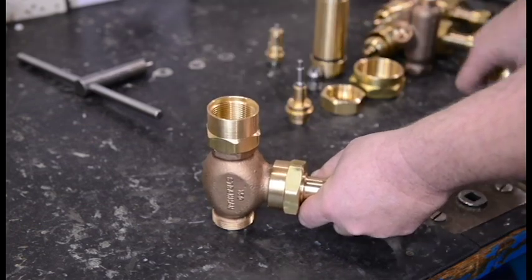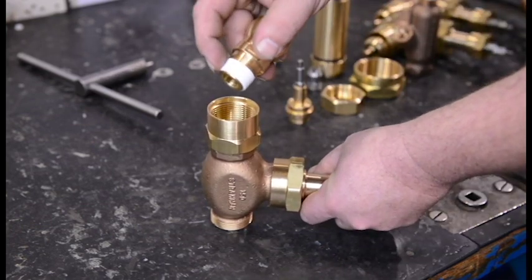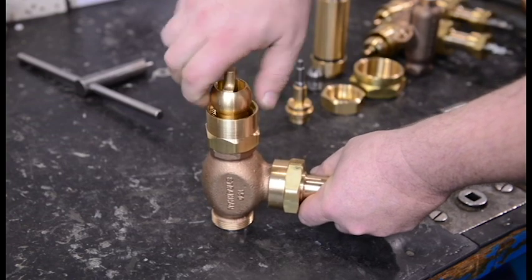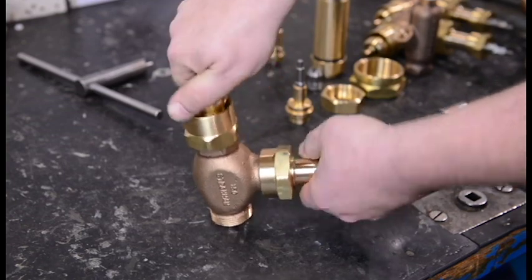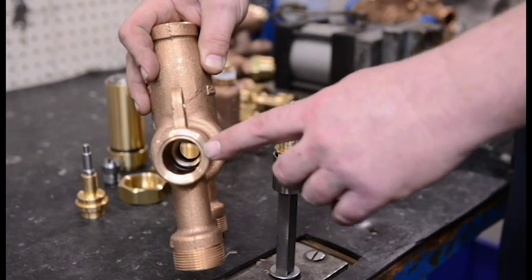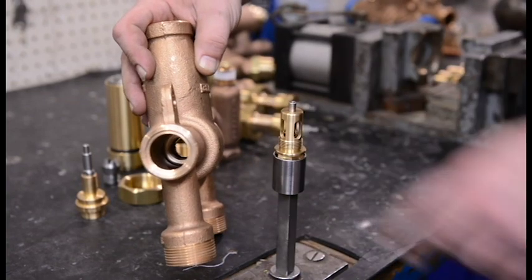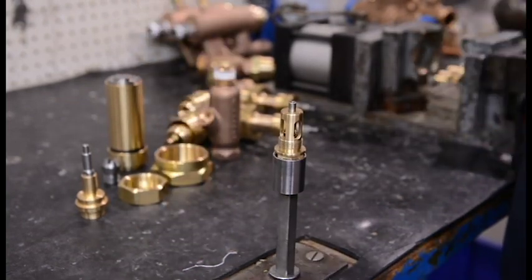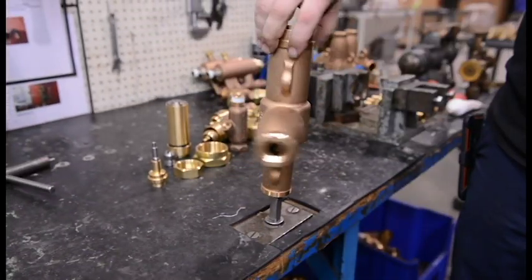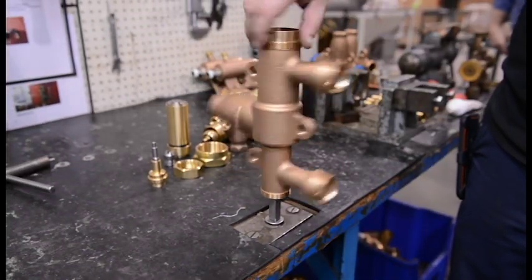Wrap pipe tape on the ball check threads. Place the union nut in position and thread the ball check into the globe valve or ball valve. Position the poppet into the poppet seat and thread into the steam side of the ball. Tighten to 25 foot pounds.